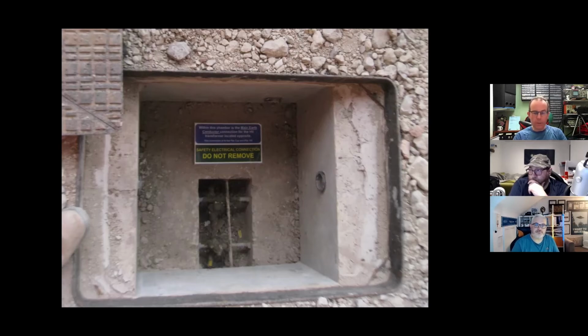About the size of these, in theory at the moment, if it's domestic, it's going to be 10 millimeter because it's basically a bonding conductor. However, with this type of foundation electrode, you get a very low resistance, typically around 1 ohm. So if there was a broken PEN conductor, think about the current that could flow. It might be an idea to size this conductor matching the size of the neutral coming in - so if there's a 16 millimeter neutral, put a 16 there. That's not actually in the regulations, but it's something to consider, because you could get fairly substantial currents flowing through this in certain conditions.